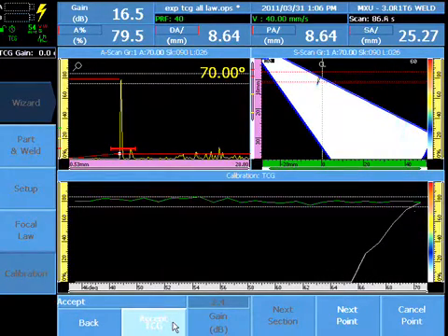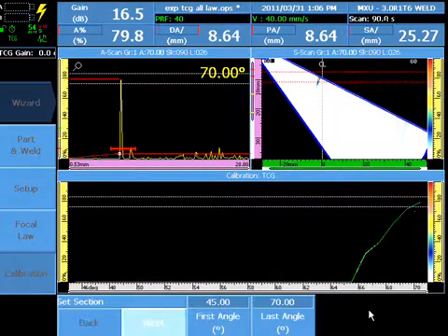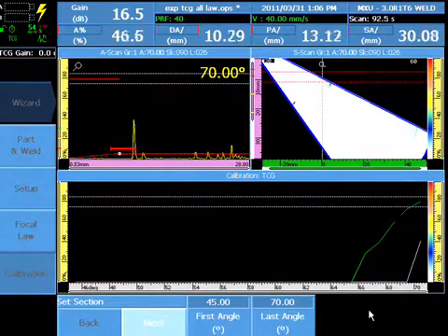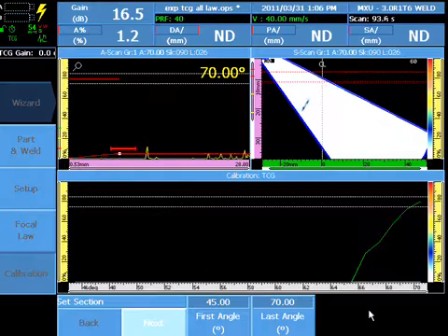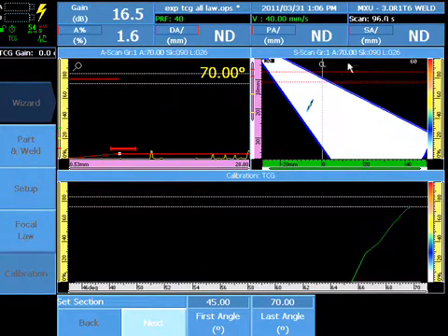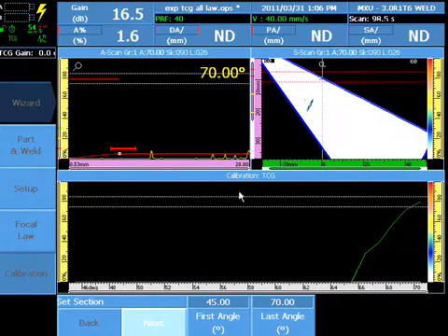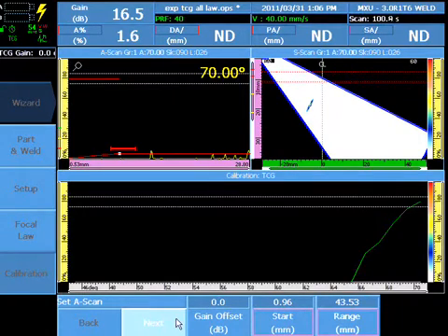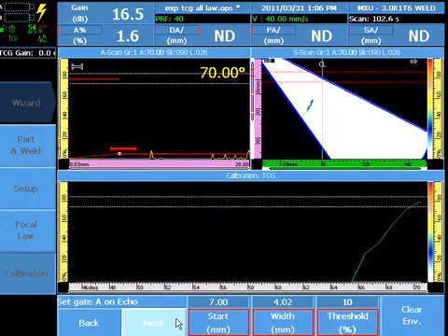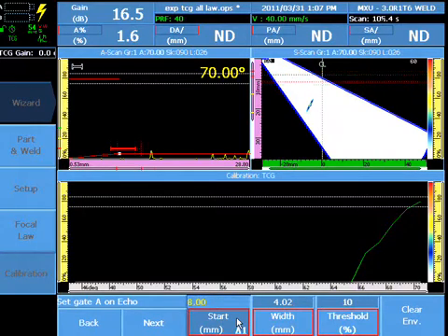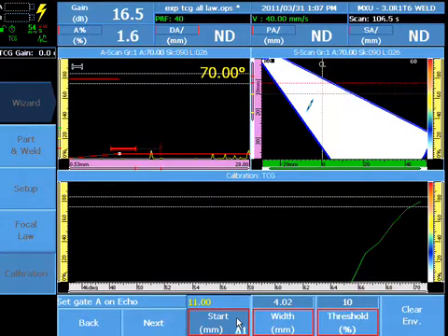Select Next Point. Manipulate the probe to the next calibration target. Move the gate position over the second TCG calibration target.